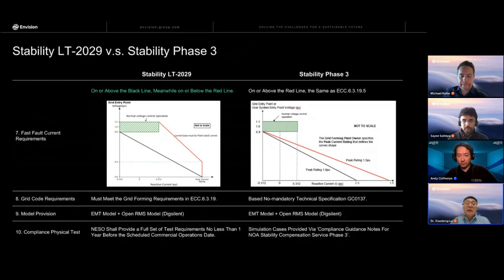And the last but not least is the fast current reinjection. Previously, only the minimum value was specified in the specification, but now the minimum value and the maximum value are both specified. So we need to make sure our current is between the black line and the red line on the left figure.